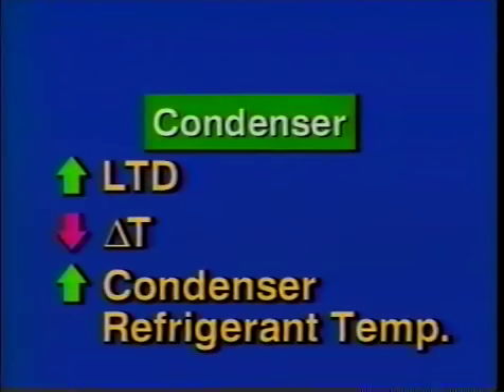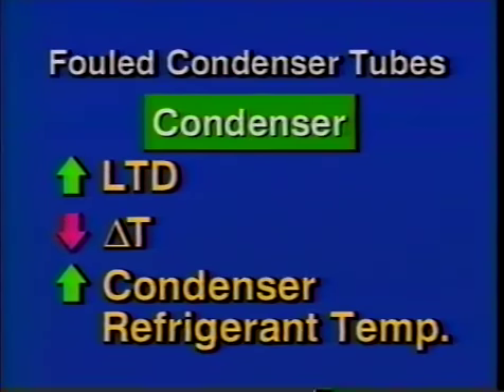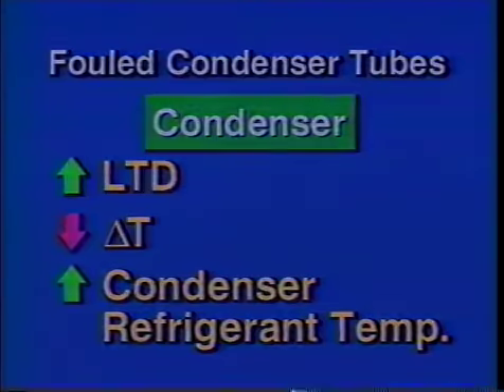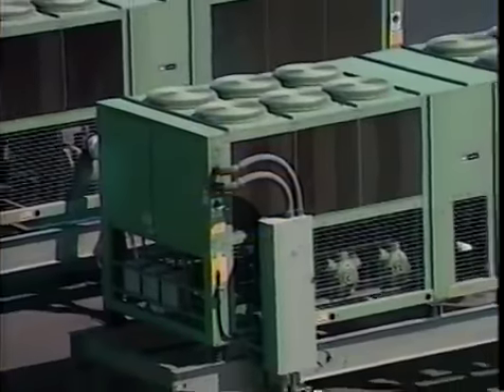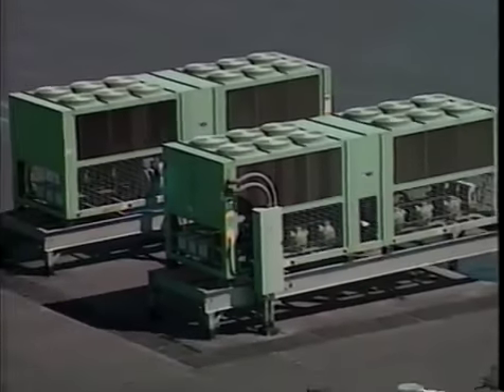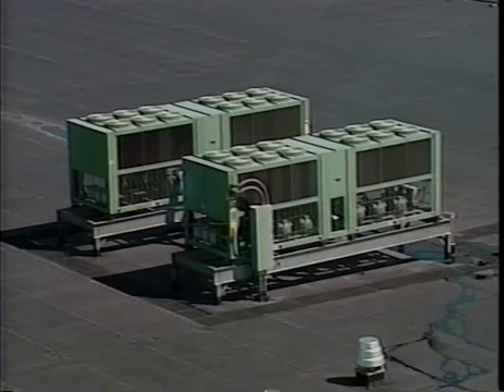This set of conditions points to inadequate heat rejection in the condenser. If this were due to low water flow, the condenser water delta T would be high, not low. Therefore, it would appear that fouled condenser tubes are the most likely culprit. Let's take a look at a chiller with an air-cooled condenser operating in a 95 degree Fahrenheit ambient. Once again, the complaint is low system capacity.